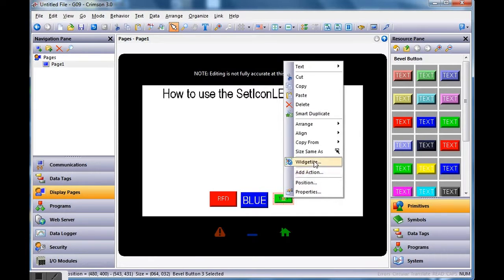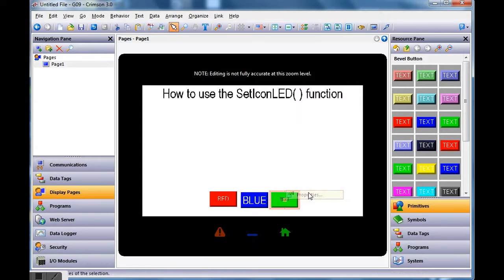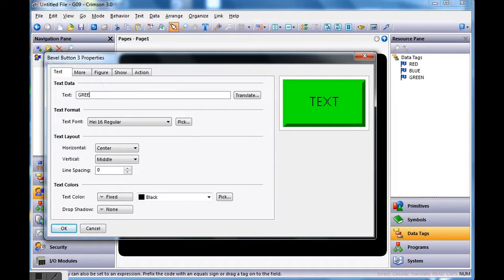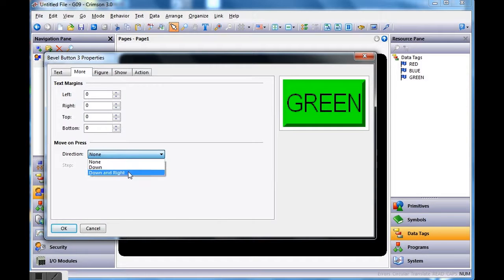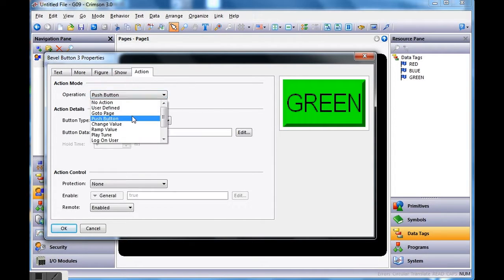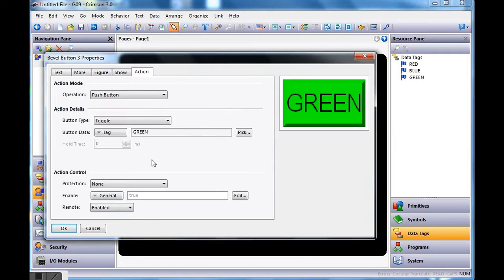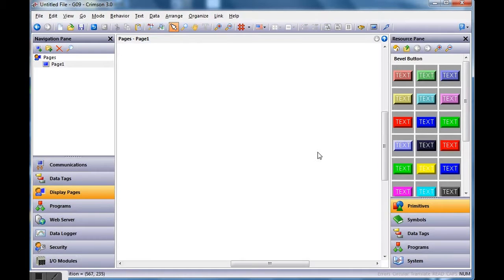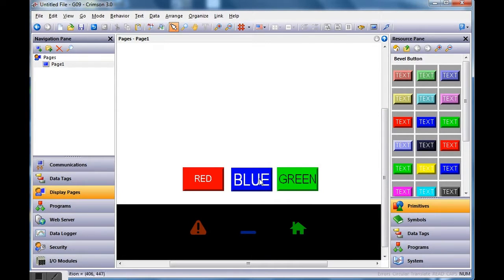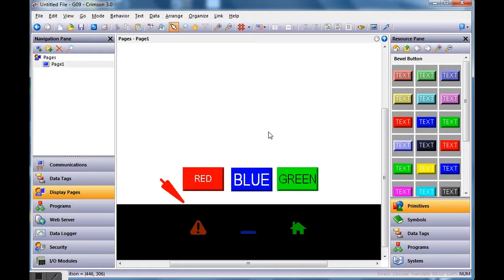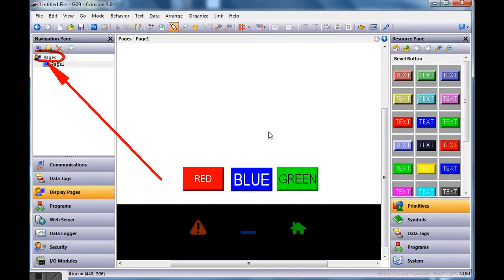I'll grab one more for the green button: right-click same size, go to Properties, change the name to 'green', make the font bigger, More tab, Action tab choose Push Button, drag the green tag in, and hit OK. Now I have my three buttons on the screen. There's one thing you have to change that's not in the documentation yet — I've made a note to redline and fix this — but in order to control these icons from the screen, you have to change the properties of the overall HMI.